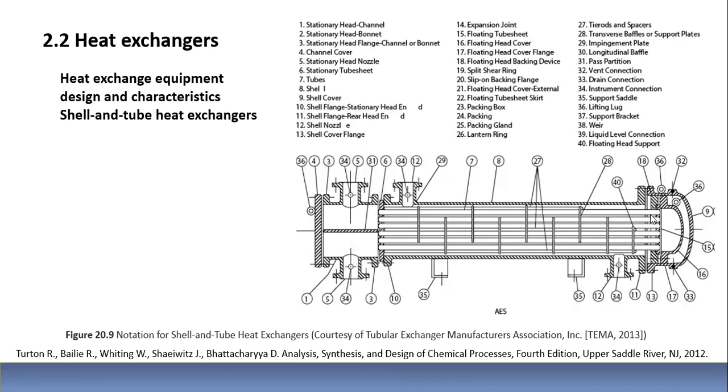Eso es bastante útil. Al otro lado igual. Saca los pernos, saca todo este cabezal y queda el tubo. Usted va a ver ahí los tubos que se encuentran aquí. Seguramente los tubos de este lado no están soldados, de tal manera que usted desaperna esto y saca toda esta tapa y se exponen los tubos al exterior. Y usted puede pasar un cepillo de lado a lado. De este lado usted puede desapernar la tapa, se abre esto y queda este cabezal totalmente descubierto, el interior, digamos, y usted lo puede limpiar.